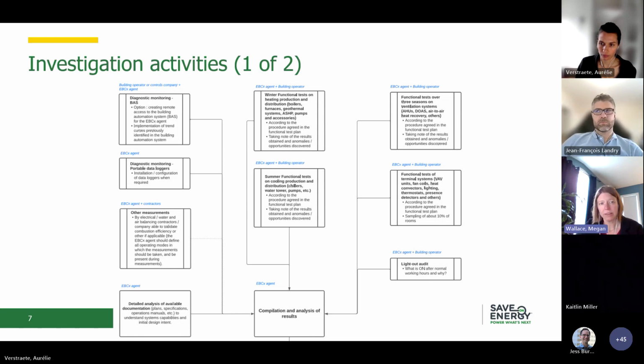If required, they can add portable data loggers as well, if there's no building control system or if they need additional information. Other measures that might be taken, the EBCX agent would do with contractors. An example of this would be air balancing. They would bring in an air balancing contractor to take air readings so that you get a better idea of how the building is working. They will also review any available documentation, so plans and drawings, specifications, operating manuals, sometimes shop drawings if they're available from the initial installation.